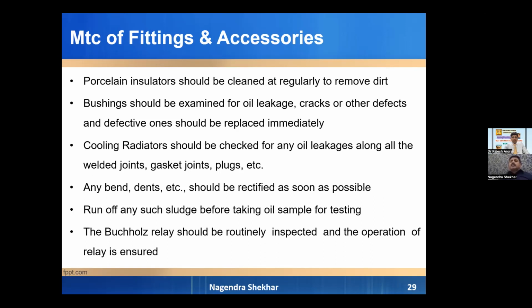If we are taking a sample for transformer oil testing, we first run off the sludge, and after running off 1 liter of oil, we then take the sample. The Buchholz relay must be tested and ensured to be operating properly.